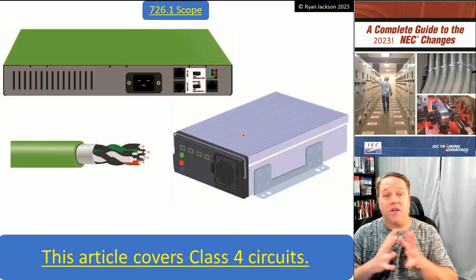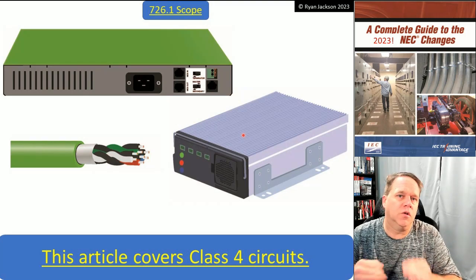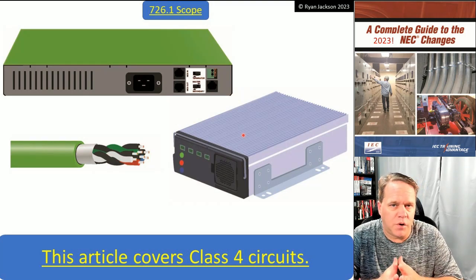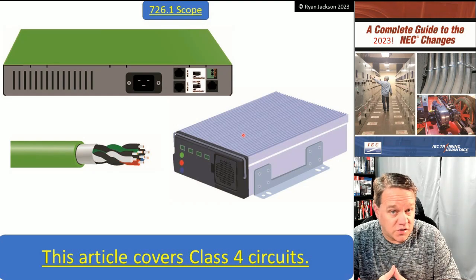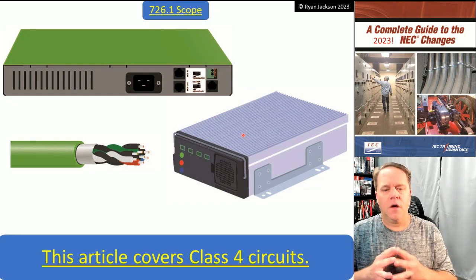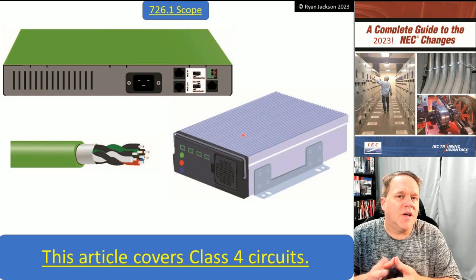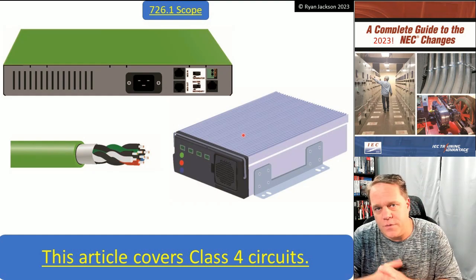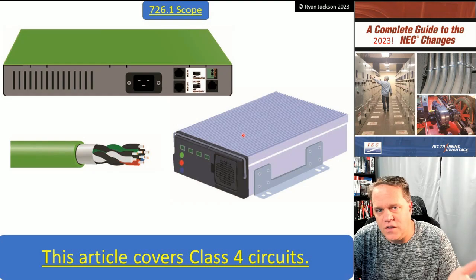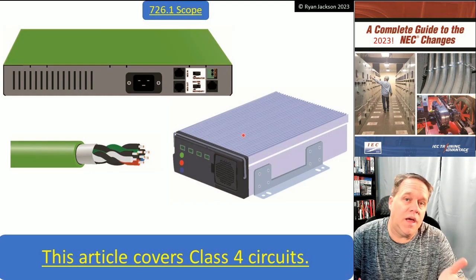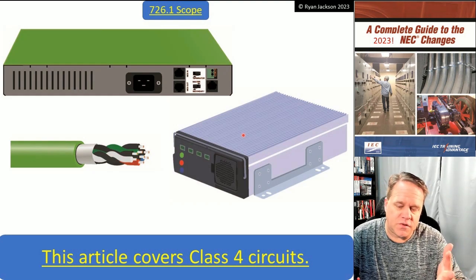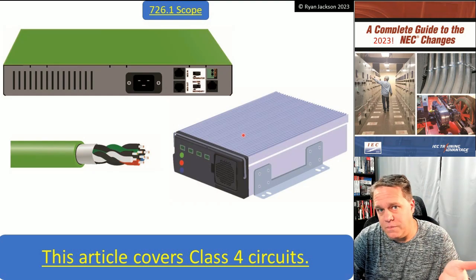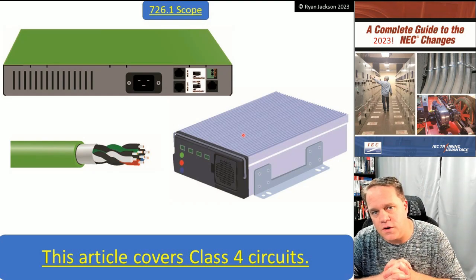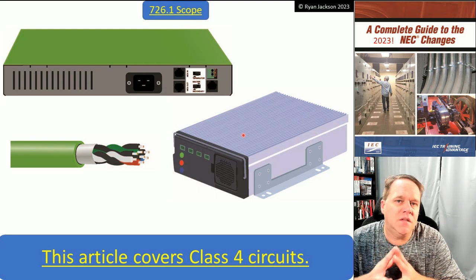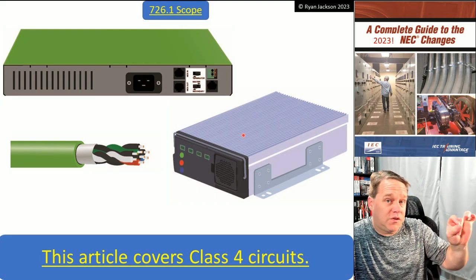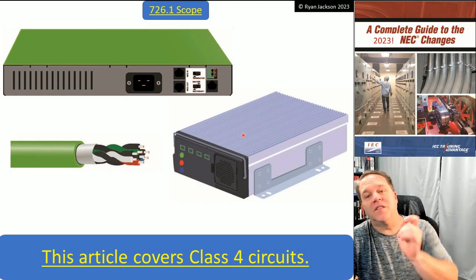Article 726 is brand new, and I'm probably going to try to do a joint video with the manufacturer of this product because it really warrants a longer discussion than I'm going to be able to have. Class 4 circuits. So we have Class 1, Class 2, and Class 3 back in Chapter 7, and now we have Article 726, which is a Class 4 circuit. And basically, it's higher amounts of voltage and power than you could have on a Class 2 or a Class 3 circuit, but it maintains safety not by the power limitation of the source, but by the technology.